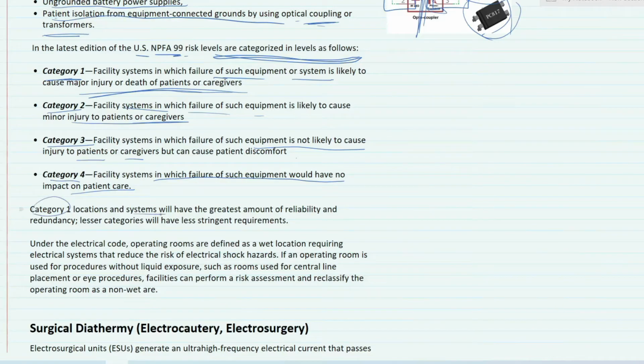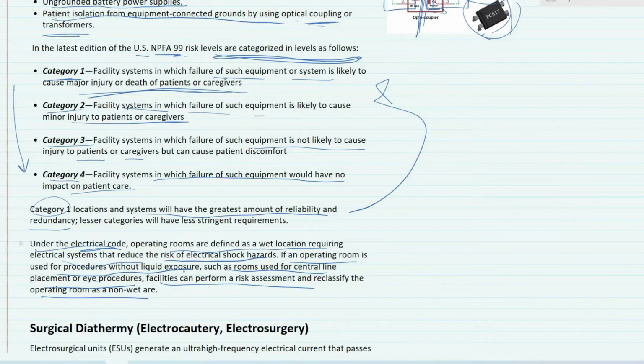Category 1 locations and systems will have the greatest amount of reliability and redundancy because they follow the most stringent requirements here. And then as the danger goes down, the requirements also go down with it. Under the electrical code of NFPA, operating rooms are defined as wet locations requiring electrical systems that reduce the risk of electrical shock hazards. Now, if an operating room is used for procedures without liquid exposure, such as rooms used for central line placement or eye procedures, which is considered non-wet, as we know that blood is a very good conductor of electricity, facilities can perform a risk assessment and reclassify the operating room as a non-wet area.